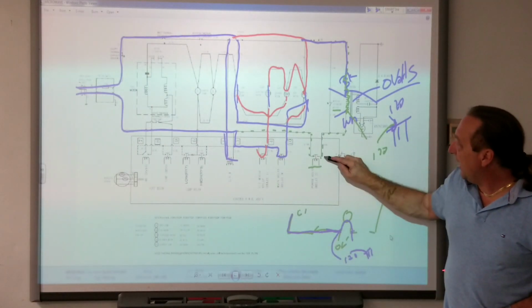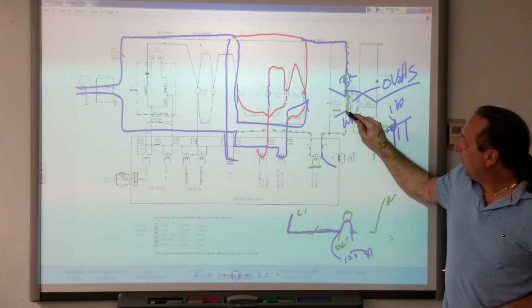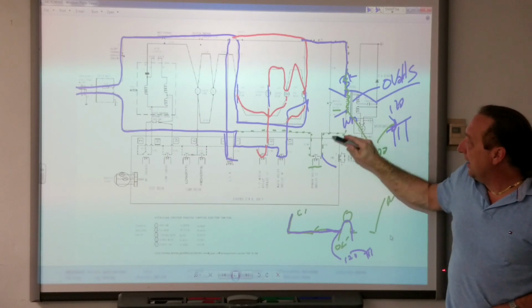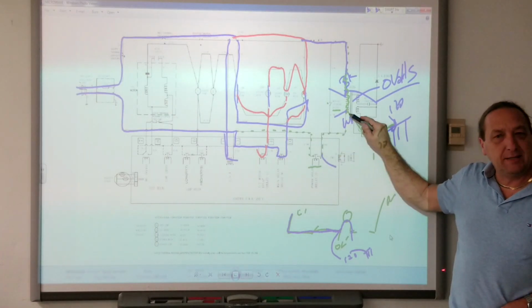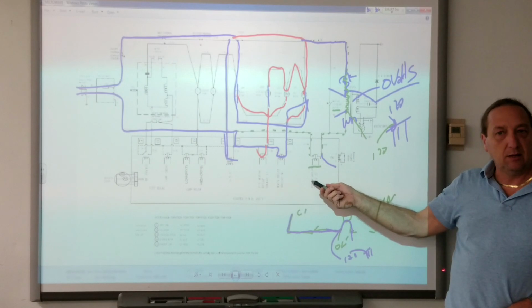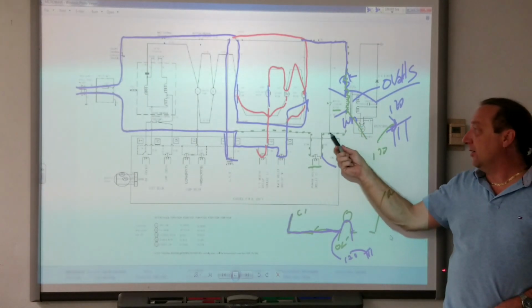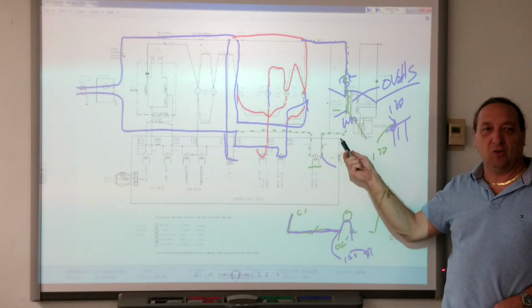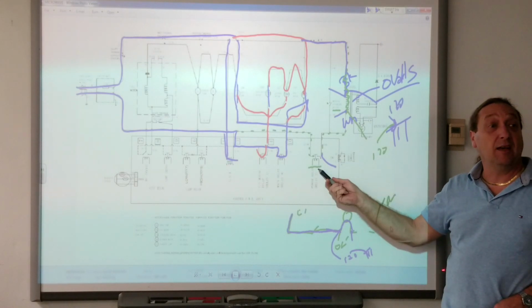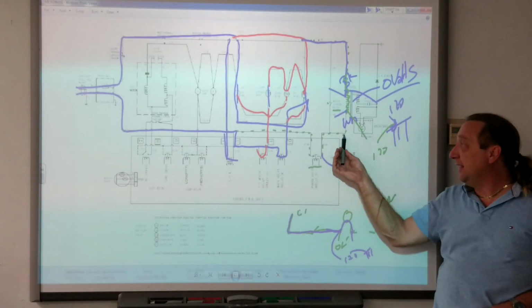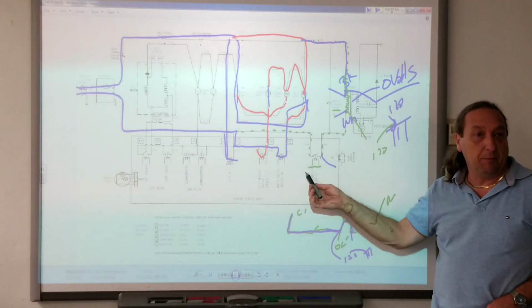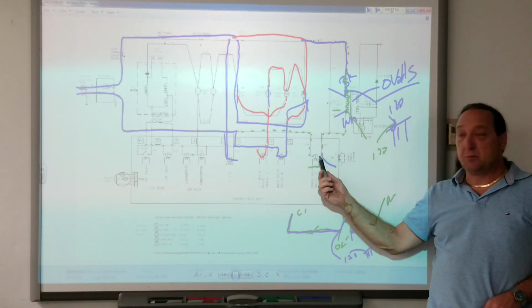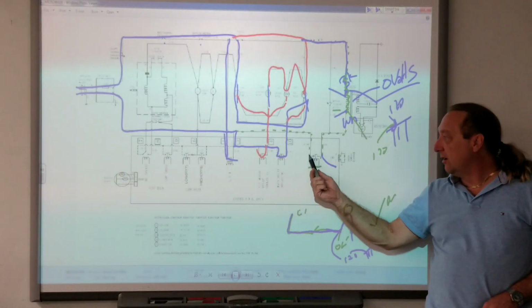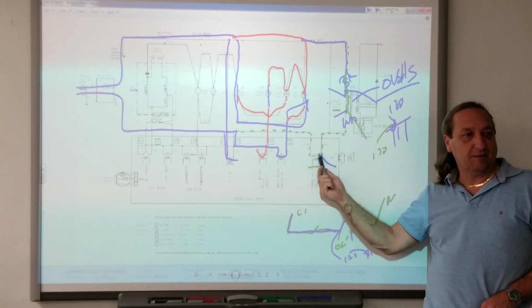So if I go here, look at the top. If I go here, from here, and I lose the voltage, what am I testing at this point? The relay? No, check those wire connections. If I lose it here, the wire's broke. If I still have voltage here, it's still feeding voltage up to this point. Maybe my relay's bad. So if the relay was bad, I won't have voltage here, but I'd have voltage here.